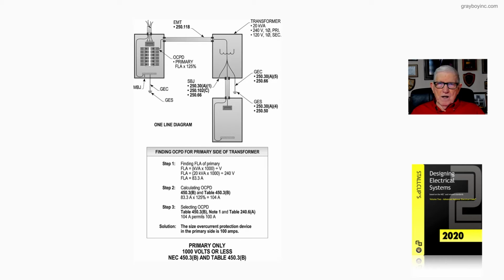above 125% or round it down. It wouldn't make any difference as long as you could energize the overcurrent device of the primary side and it wouldn't trip due to the inrush current. Now, when we basically review this transformer here, we have the primary overcurrent device, as you see in the illustration, at 125%, and the conductors at 125% to supply that primary.